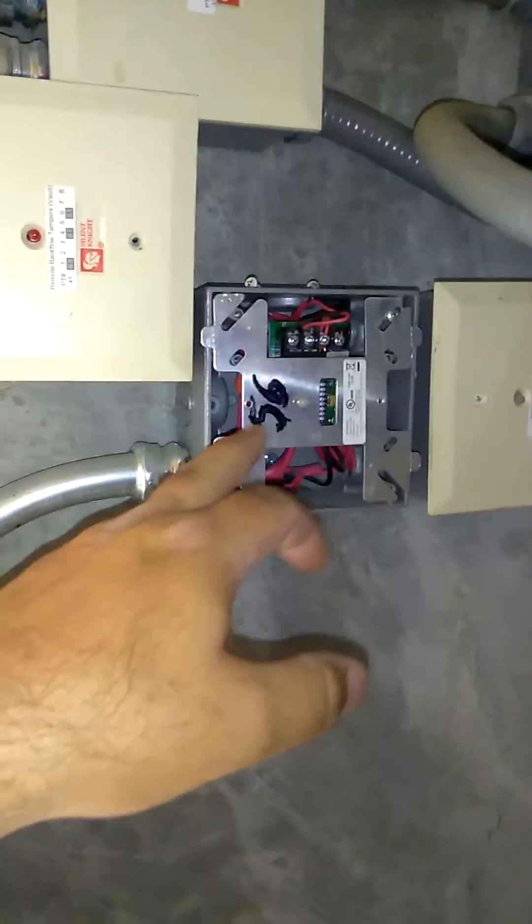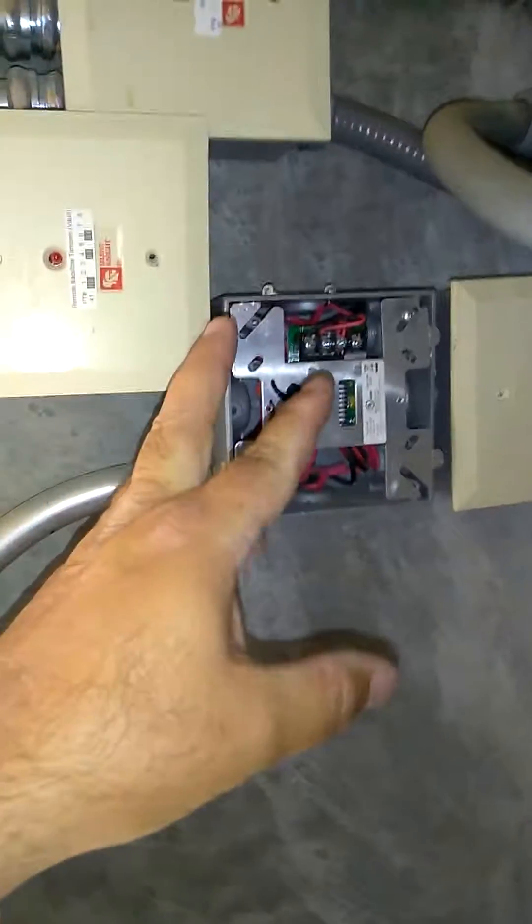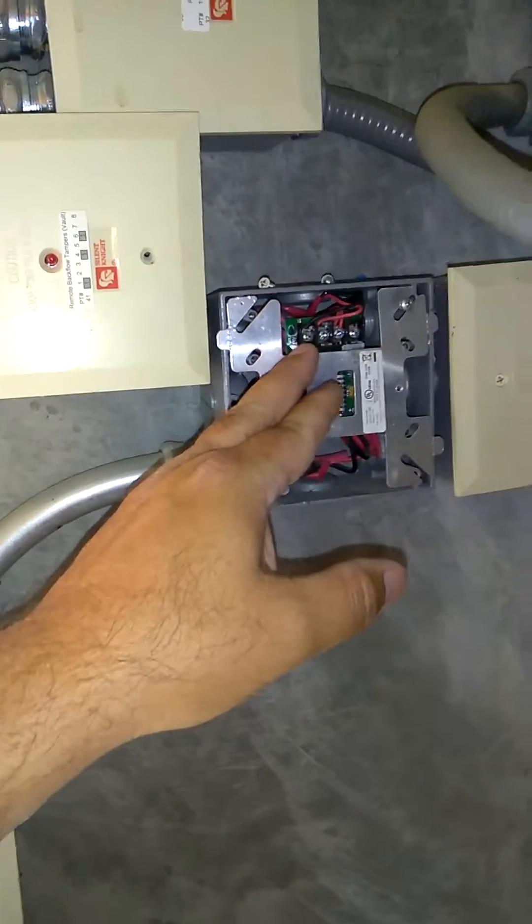Okay, I came out of here — trouble was on this module. It was lit up solid. I took it off, disconnected the wire, checked the ohms across the wire. It definitely had a dead short.